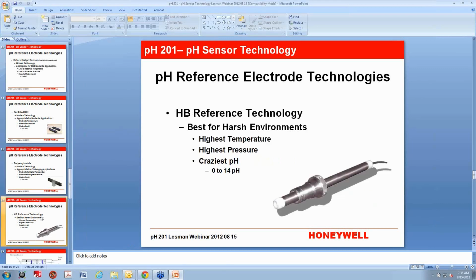The last technology up is the HB reference technology. This is a picture of a ball valve insertion style HB sensor. The HB reference technology is really best for harsh environments. It will work in any situation except for high purity pH. And I'm going to show you a little drawing of how it works. These have the highest temperature pressure ratings in the industry. They can go as high as 150 C in a particular body, which we only manufacture as a special. Our regular ones go up to 140 C. And they have the highest pressure ratings in the industry. If you put it into what's called a pressure monster body, which is a stainless steel or Hastelloy or titanium body that threads into the process, it's not ball valve insertion.